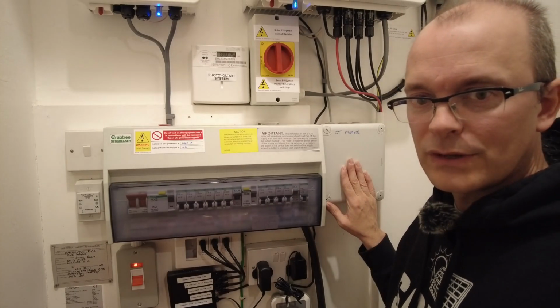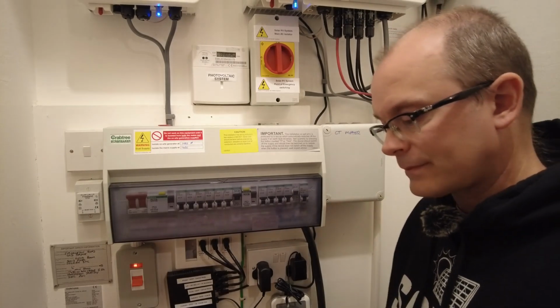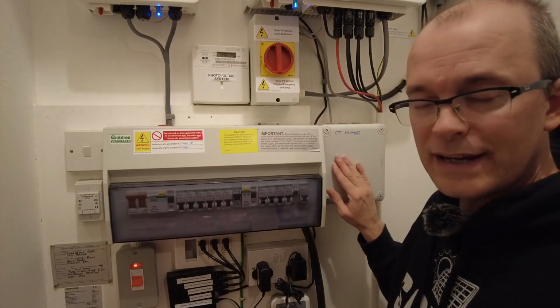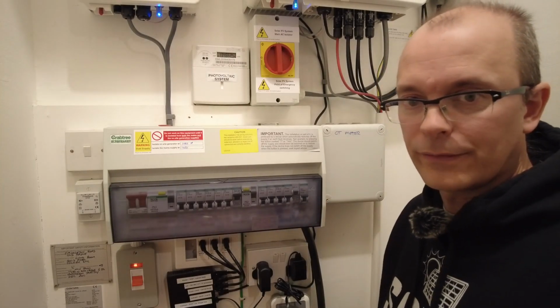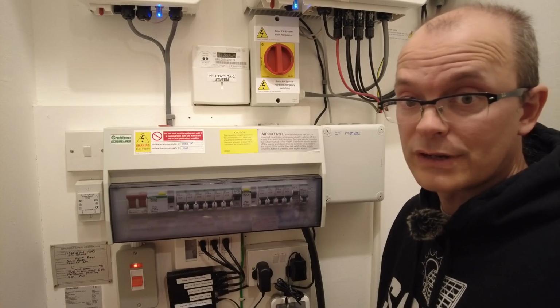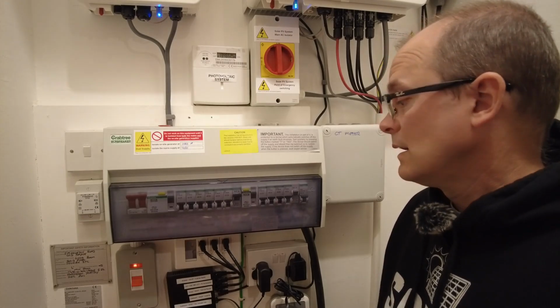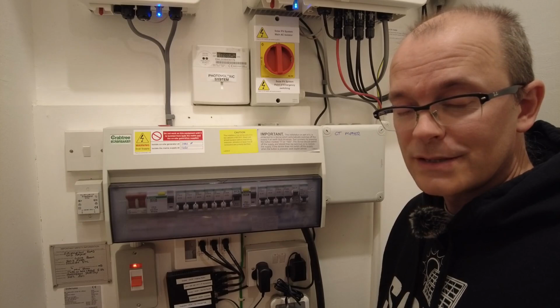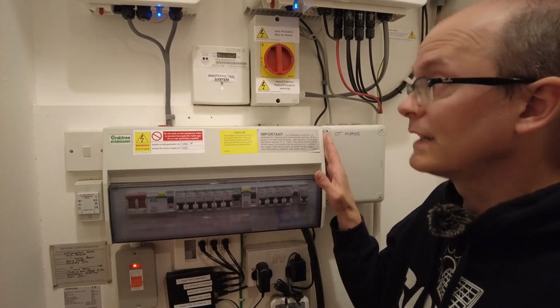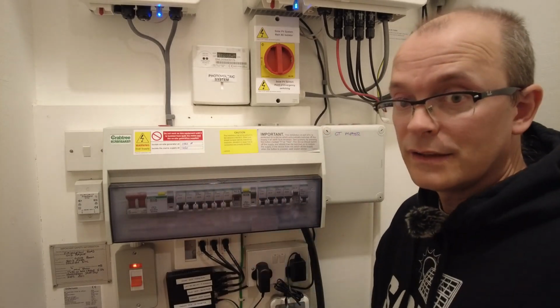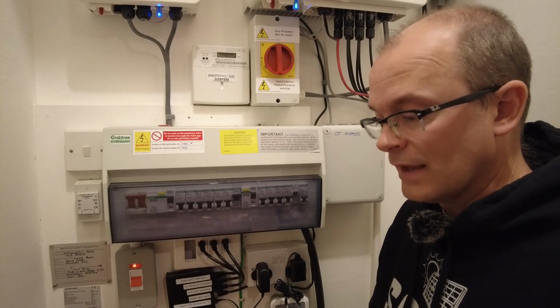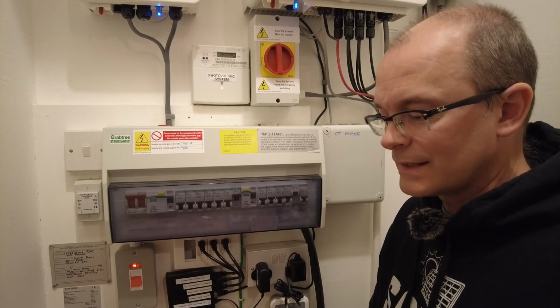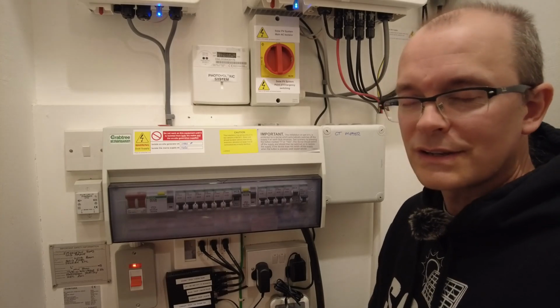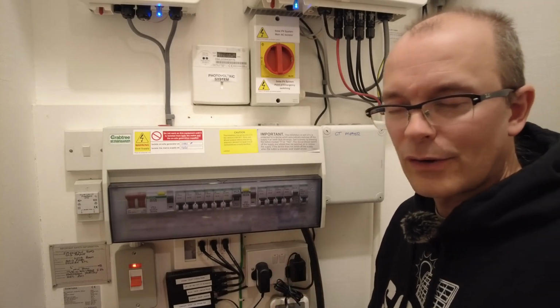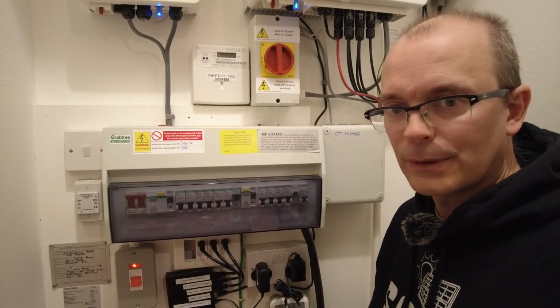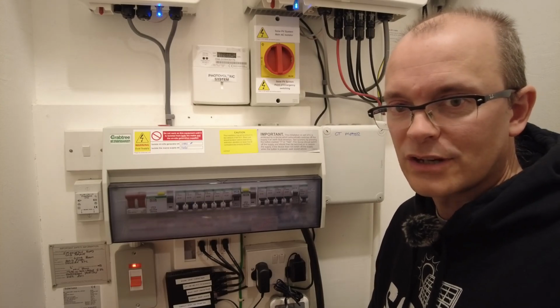In here, we've got the import-export meter. There are 3 channels for 3-phase current transformer measurements. Only one of those channels is used for the single-phase incomer for measuring the grid. The other 2 channels are spare. So my thought is that you could use one of those other 2 channels and put a current transformer around the supply going to the electric car charger.